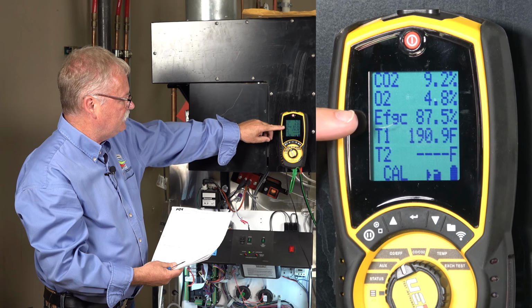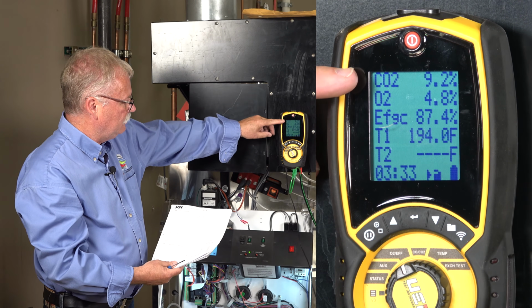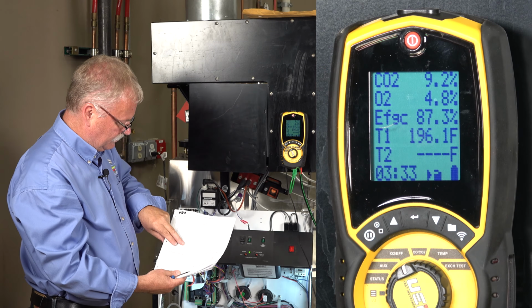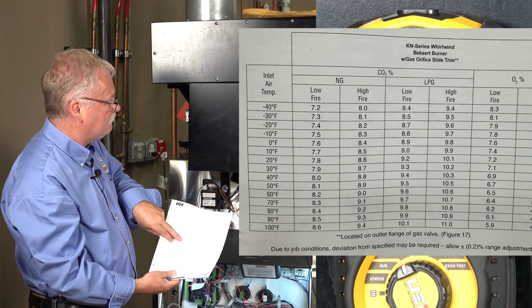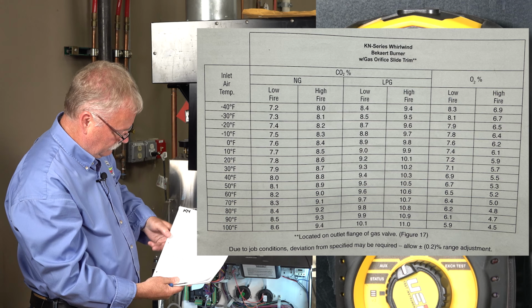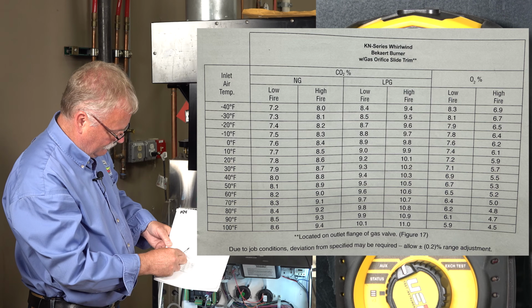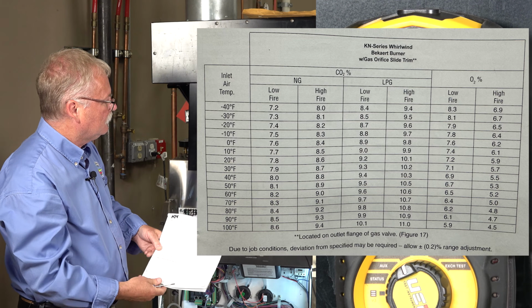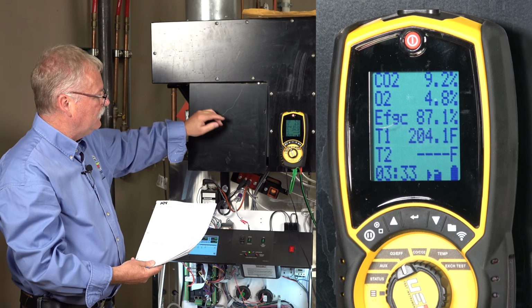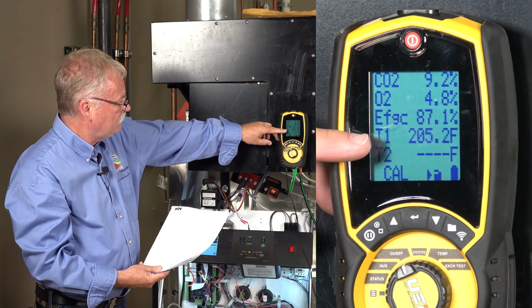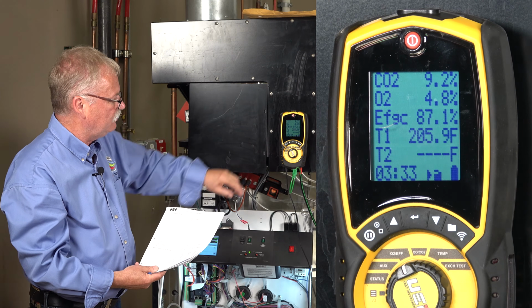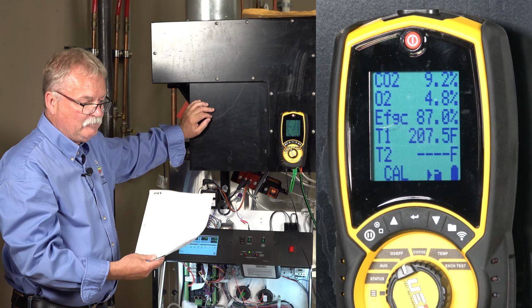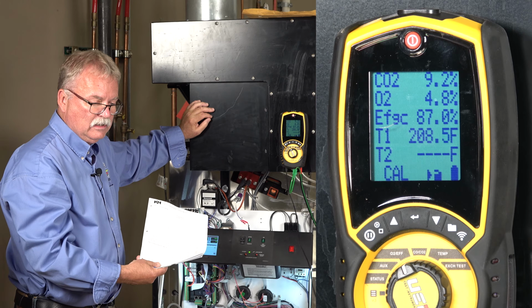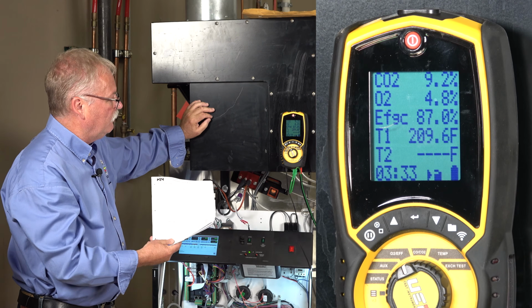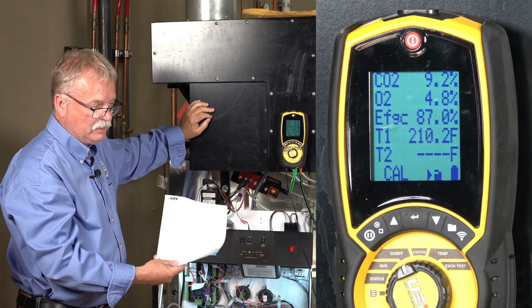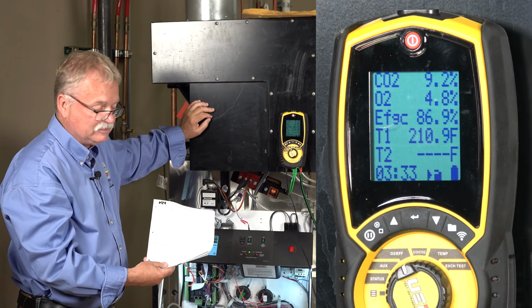As you can see, our efficiency is going down. Our CO2 is going up a little bit. It's actually almost right in the range that it should be. 9.2, I'm looking at 9.2, 9.3. I'm right here. As you can see, efficiency goes down, stack temperature goes up. We are not dumping as much heat into our system. More of it's going out the stack right now because we have a much bigger burn, more BTUs we're throwing into the system.